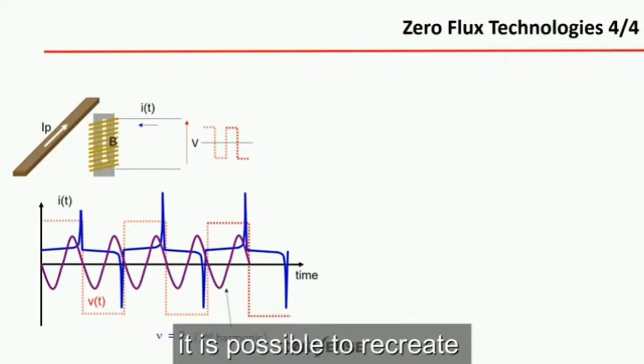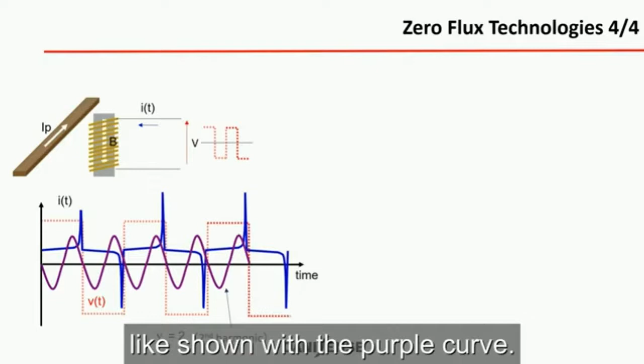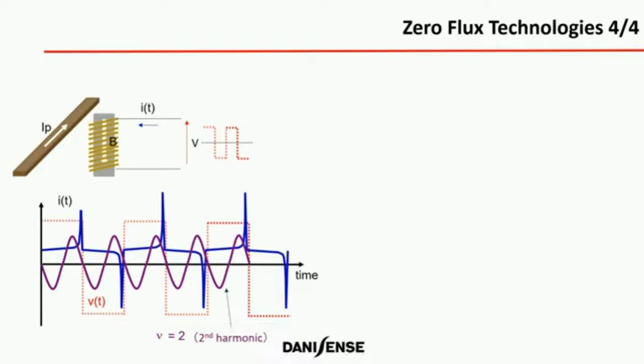Finally, by using a signal processing calculation called second harmonic, it is possible to recreate the primary current signal, as shown with the purple curve. That's basically how the zero flux principle works.